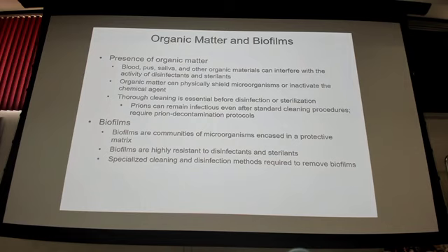So when it comes out, it's going to have caked-on blood and whatever other bodily fluid was on that instrument. So before you put something in an autoclave that has tissue or blood on it, you have to remove that organic material completely before it goes in. I have an example pretty soon, in a couple of slides, of that going wrong on an epic scale.